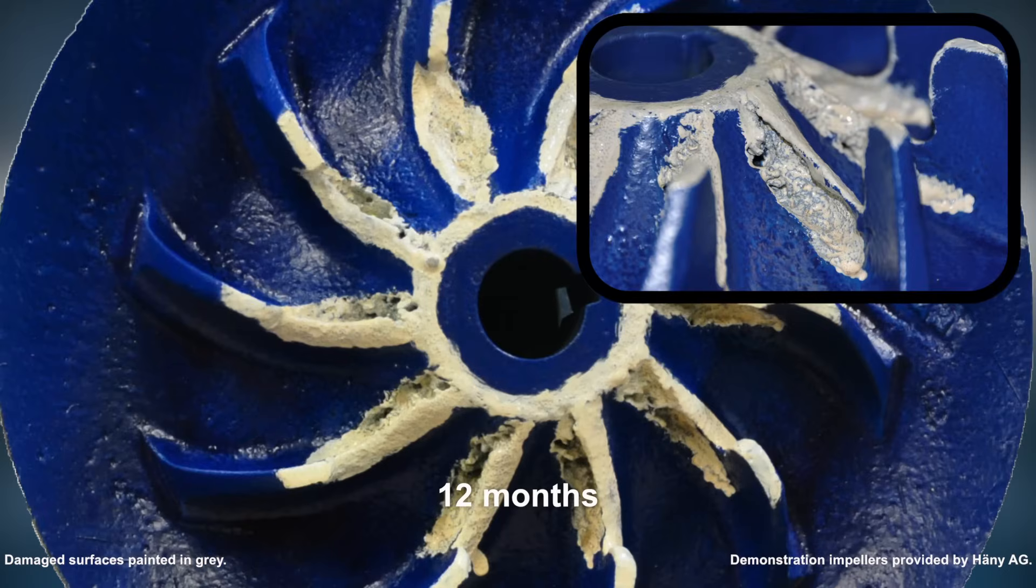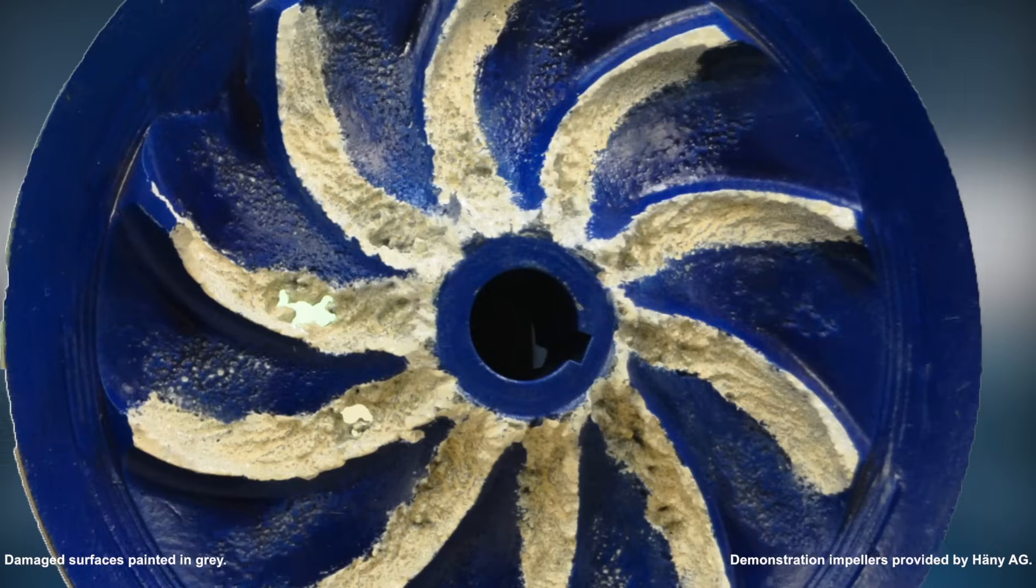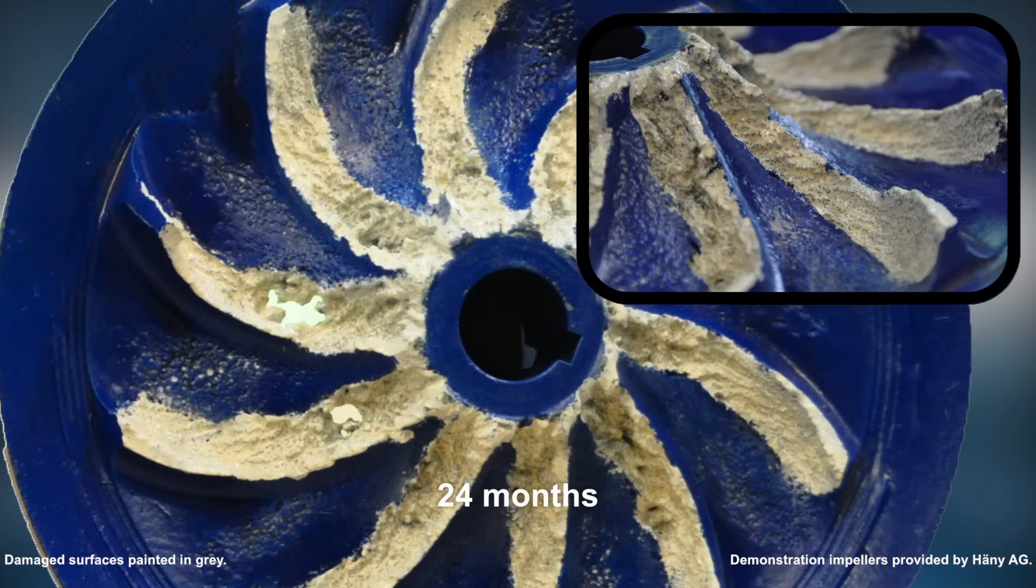After a year of operation under cavitation, the damaged geometry has a different shape and therefore the flow has a different pattern. The collapsing cavitation bubbles cause material break-off at the top edge of the blades. After 2 years, the blades have been eroded completely, which makes it impossible for the pump to function.